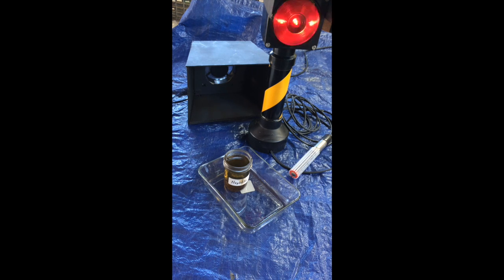So I'm going to reach over and see if we can reset the sensor. If we can, then we'll proceed to the naphtha test, using naphtha instead of crude oil. Naphtha is, of course, a little bit more convenient and available than is crude oil, but earlier tests have indicated that the sensor does very well in not only naphtha, but gasoline, jet fuel, diesel fuel, and crude oil. So first, let's see if we can reset the flasher. And we can. That indicates that the sensor probe is out of the brine, so there's no conductive pathway to be detected.